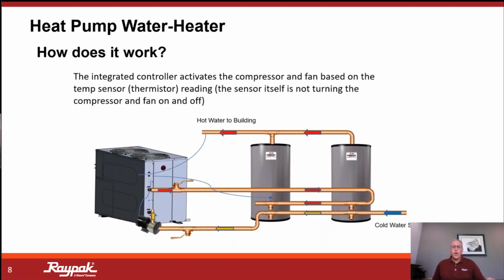How does it work? Well, we're going to register a call for heat. Typically, a sensor in the tank is going to tie into this unit, much like you would with a natural gas or propane heater, or even electric. If it has a set point and it falls below set point minus the differential, we're going to actuate a call for heat, if you will. In this instance, domestic water. So if this tank has a set point of 140 degrees with a 10-degree differential, as hot water leaves the tank and cold water fills the tank, we're going to draw down in temperature. We're going to get to that 130-degree temperature. We're going to actuate a call for heat to a unit or units, plural. We're going to engage the circulator. We're going to start pulling flow from the tank and our cold water supply, as the case may be. And we're going to start harvesting the BTUs out of that ambient air and we're going to place them into that tank.